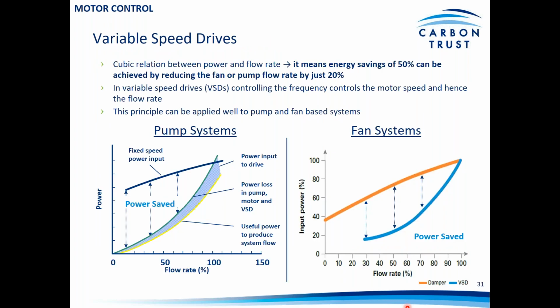So looking at variable speed drives in more detail, we have an example here on the left of a pump system. And you can see here the profile of energy use relative to a change in flow rate at the top for a fixed speed motor. There is a slight reduction as the flow rate changes, but it's nothing in comparison to the change that you see through a variable speed motor. You can see there the profile of the energy use changes dramatically as we come down the curve and as the speed reduces to match the flow rate. So there's significant power savings to be had, as can be seen in the graph there, and that cubic relationship that we saw on the previous chart means that typically what you can see is savings of 50% achieved by reducing fan or pump flow rate by just 20%.